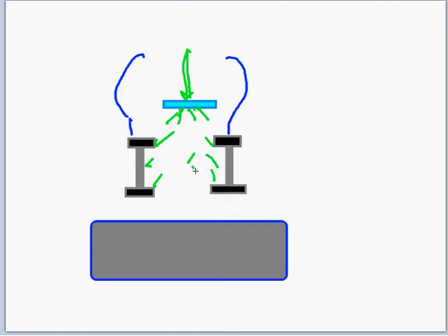So they're moving in a lot of different directions. They're definitely moving down towards the patient, but they get scattered in the air as well. So even after leaving here, they're coming out relatively straight, but right away they're hitting air molecules and spreading out. So that's why, first of all, you like to have this collimator as close as you can to the patient. And the electrons are really not coming down in just perfectly straight lines like the photons are.